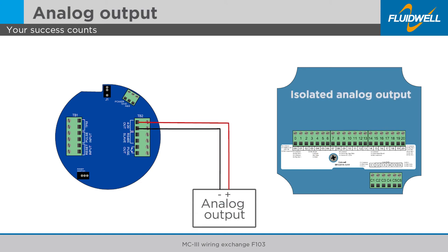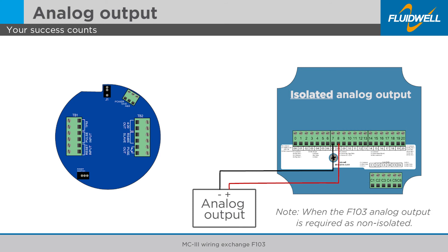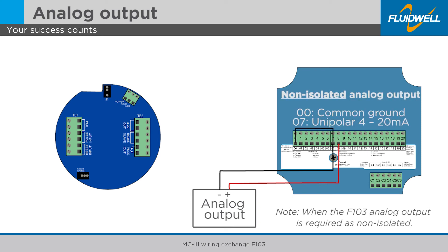Disconnect the positive analog output wire from the MC3 and connect it to terminal 7 of the F103. The F103 analog output is isolated to suit all customer systems. The MC3 is not isolated. If the F103 analog output is required as non-isolated, connect terminal 7 to common ground.